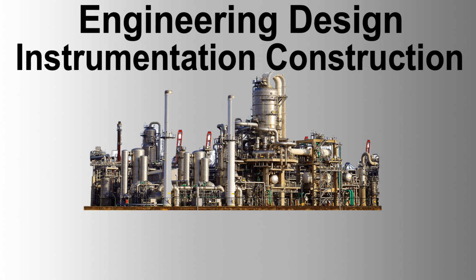Instrument connections. All instruments shall have their own individual tapping, except where shown on approved drawings. Combining of instrument tappings, such as a pressure transmitter connected to the HP connection of an orifice plate, shall not be allowed. Locally mounted pressure gauges shall be installed in accordance with the relevant hookup drawing.